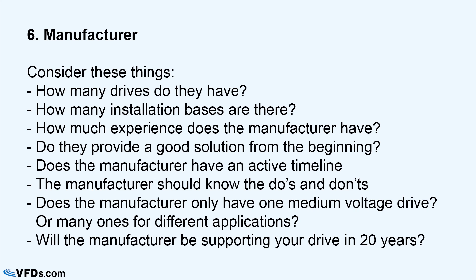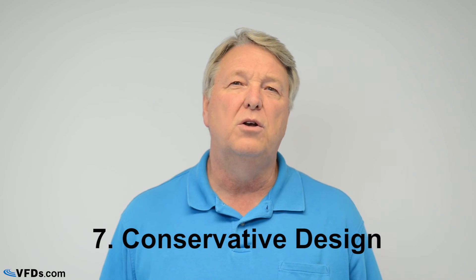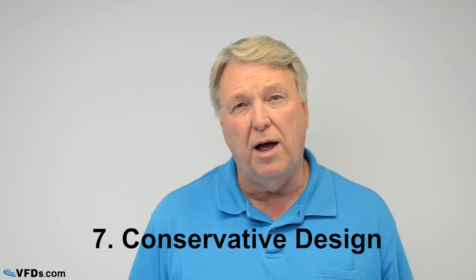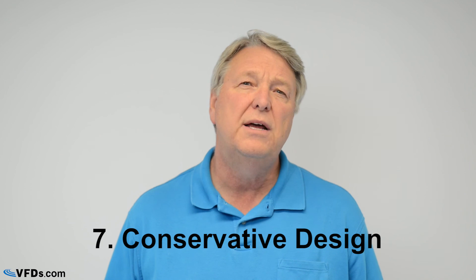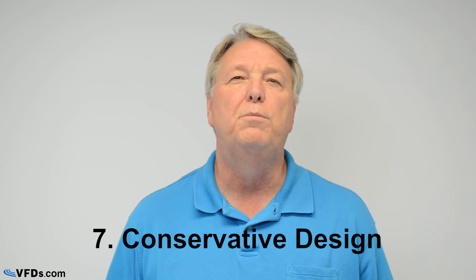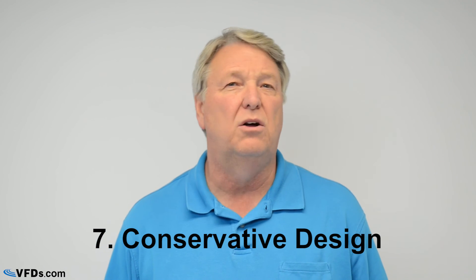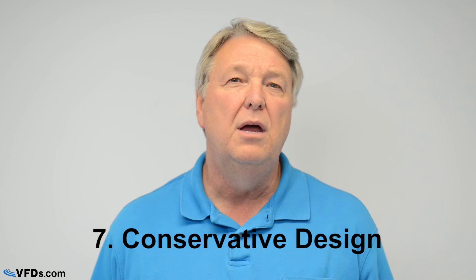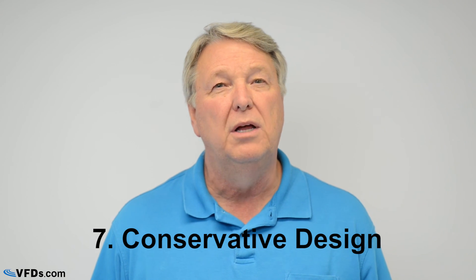Point number seven has to do with conservative design. As a simple example: if you have a 100-amp drive using 100-amp transistors, that's not conservative. Using 110-amp transistors is a little more conservative; 120 or 150 would be more conservative yet. These principles apply to transistors, diodes, conductors, capacitors, heat sinks, and all sorts of components. Manufacturers supplying drives for tough applications requiring high reliability and frequent overloads have likely designed their drives to be very reliable in difficult conditions.